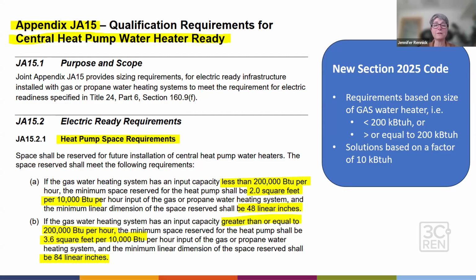And the space heating requirements, for example, are going to be based on 2 square feet per 10,000 BTU per hour of your heating system, and it gives you a minimum lineal dimension of 48 inches. But for the bigger system, that's going to bump up to 3.6 square feet per 10 kBTU per hour of your installed system. And you have to have a minimum lineal dimension of 84 inches.